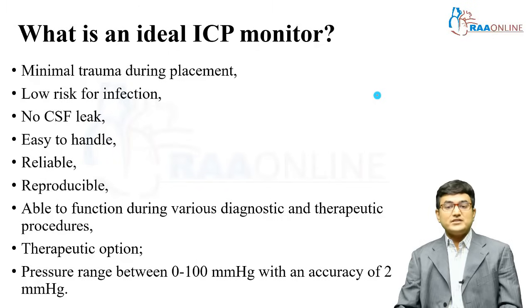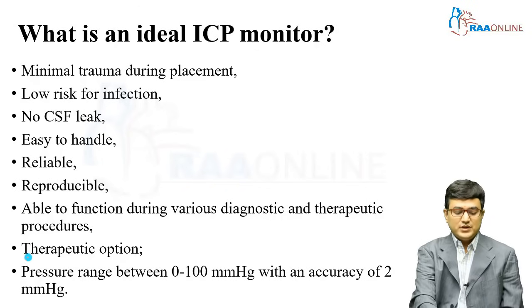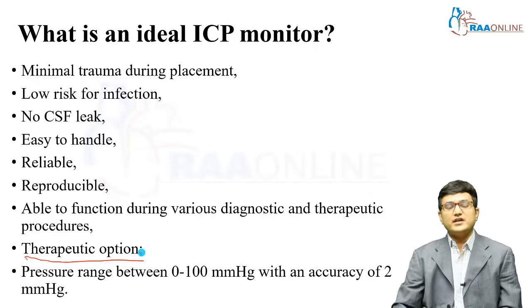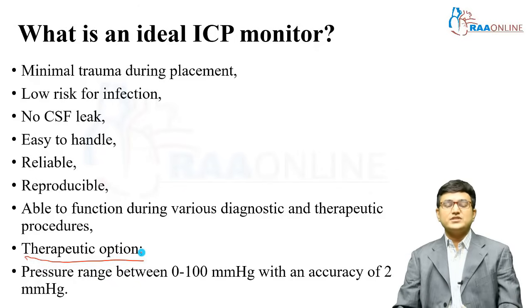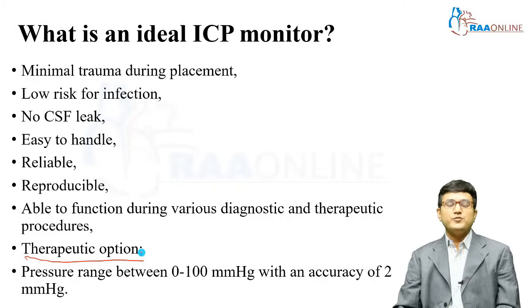An ideal ICP monitor is not only diagnostic but also provides a therapeutic option. An external ventricular drain, for example, allows CSF venting when pressures rise. The pressure range it measures should be 0 to 100 mmHg with an accuracy of 2 mmHg, especially in the 0 to 20 mmHg range of normal ICP values.